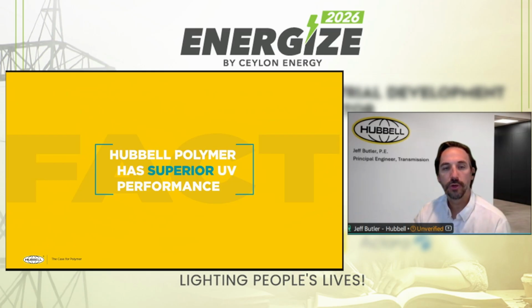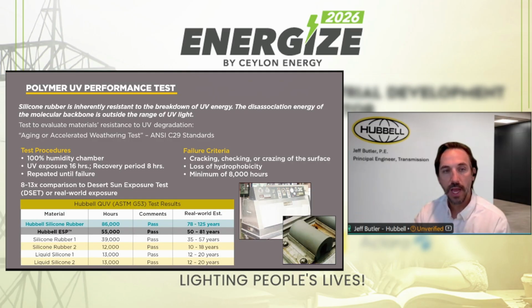Now, I was talking about UV that comes from the sun, as well as UV that comes from the electrical activity of the corona discharge that I was just referring to. So the test that was performed here is often referred to as a QUV test, and it's performed in a chamber where you have 100% humidity, you have a period of exposure with a period of recovery, and it's similar to another test that's referred to as the DSET, or the Desert Sun Exposure Test. And that's the way that we can try and relate these hours of this test to real-world estimated lifespans.